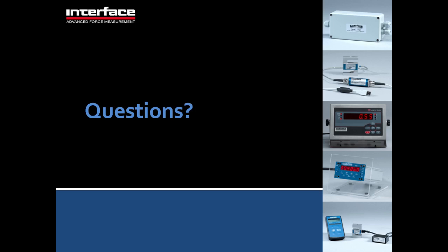Please explain bit resolution. This could be lengthy. Oh, now we'll keep it brief. Digital instruments convert the analog signal to digital in something called an analog to digital converter. And those converters have a number of bits associated with them, typically 12-bit, 16-bit, and we're starting to see a lot of 24-bit converters. Basically what that means is it chops the signal into a certain number of pieces. 12 bits is about 4,000 pieces. 16 bits is 64,000 parts. So 16 bits is typically adequate. Some of our instruments have 24 bits. Some of them can make use of those extra bits. Some of them cannot. And so a million bits doesn't do any good if most of them are noise. So typically somewhere in the 18-bit range is beginning to be the limit of usable resolution. But it's basically how many pieces the input signal is chopped up into, and it limits the resolution of the device.